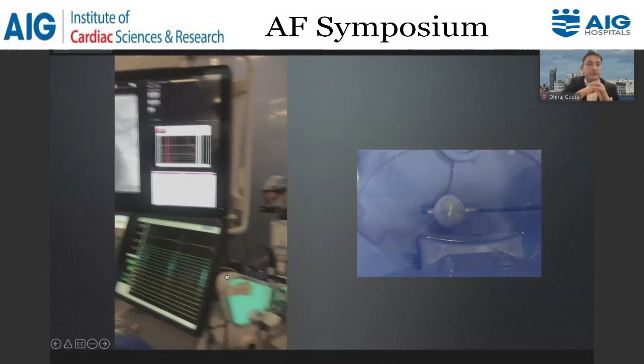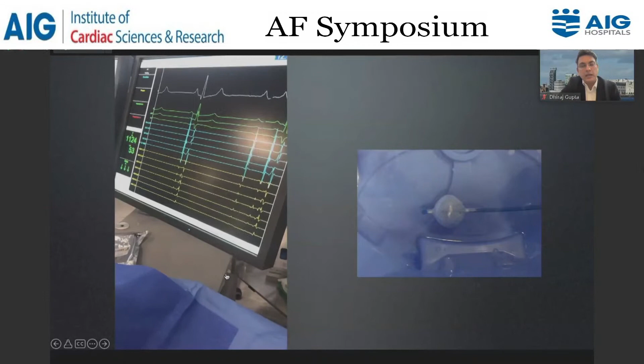And you can see we also rely very heavily on the trajectory of the temperature drop. So if the temperature is dropping promptly and very well, as you can see here, usually we say if you reach minus 30 degrees at 30 seconds, you've got a very good seal and you're going to get a very good end result. So we look at that, and that guides us very nicely. If we don't get a good seal, i.e., if you don't reach minus 40 degrees by 60 seconds, we would stop. We would re-occlude the balloon and we would go again. It's better to get one excellent quality freeze rather than lots of mediocre level ones.